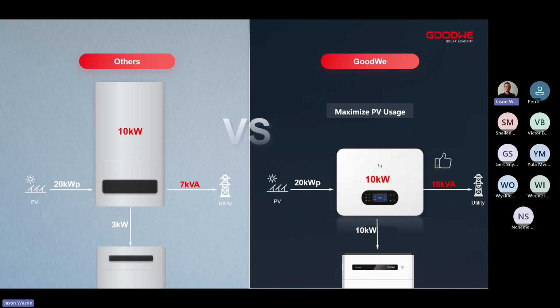Okay, so like I mentioned, we do have the maximum PV usage of 200% on all of our inverters, so double the PV capacity of the inverter's nameplate. So on 10 kilowatt units, we can use 20 kilowatts of PV on the inverter. On a 12 kilowatt unit, we can use 24 kilowatts of PV. If we look on the left-hand side, this is just a generic inverter where we would have a 10 kilowatt unit with 20 kilowatts of PV put onto the inverter.